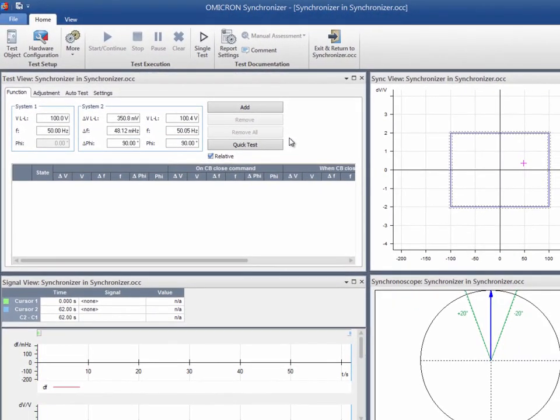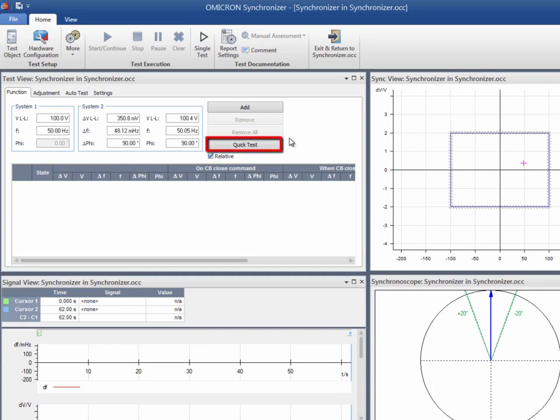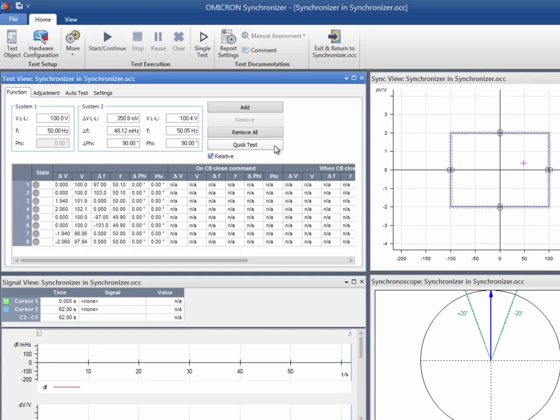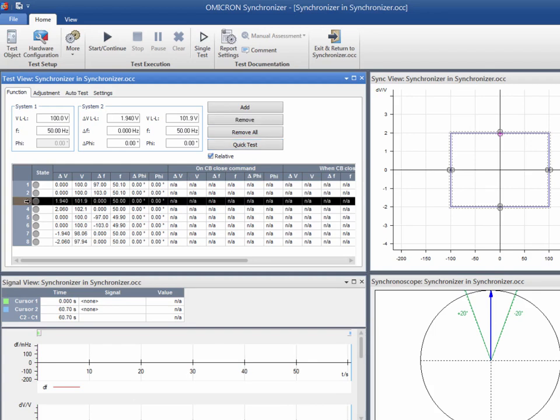To get points into the table, you can either use the input fields or add a point directly from the sync view. Use the Quick Test option to add a total of eight points at the tolerance borders. This is a quick way to insert meaningful test points into the test table. We will use the Quick Test option, but we will shift the points where the frequency difference is zero. This is because the relay requires a certain frequency deviation to work properly.